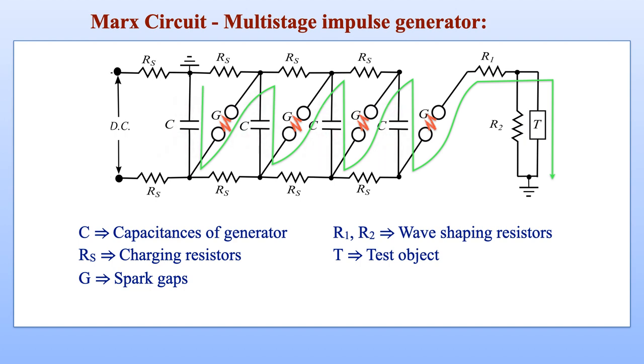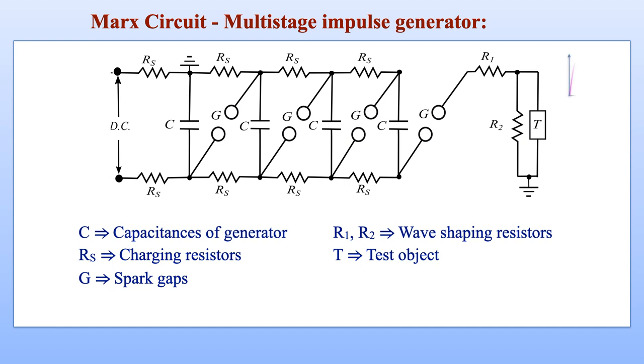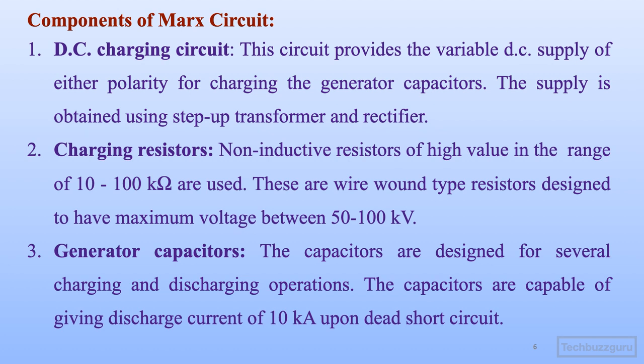Consequently, the capacitors will discharge through the spark gaps and energy stored in the capacitors will be delivered to the test object as an impulse voltage. As the energy is delivered to the test object, the capacitors get discharged and hence the spark gaps will also extinguish after the impulse has appeared across the load. This is the basic operating principle of a multi-stage impulse generator.